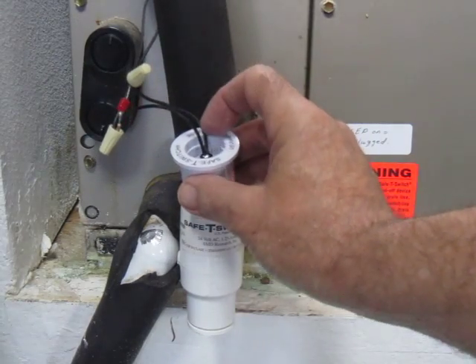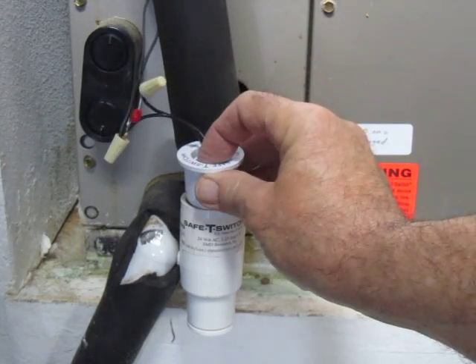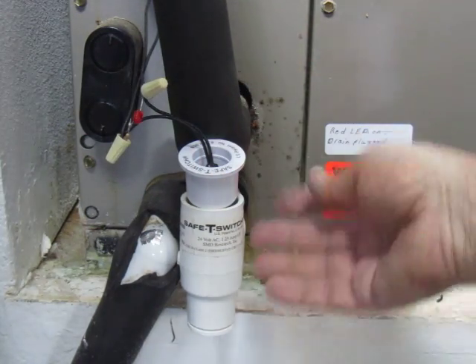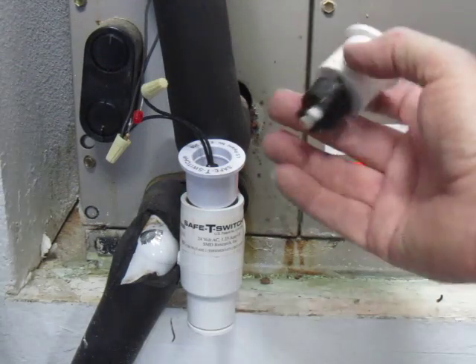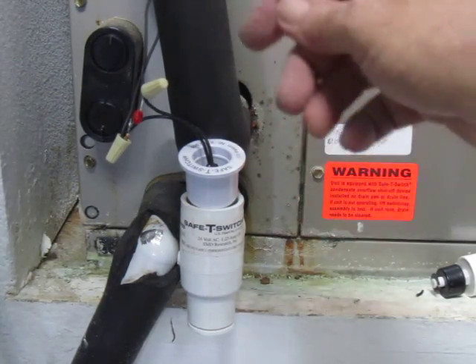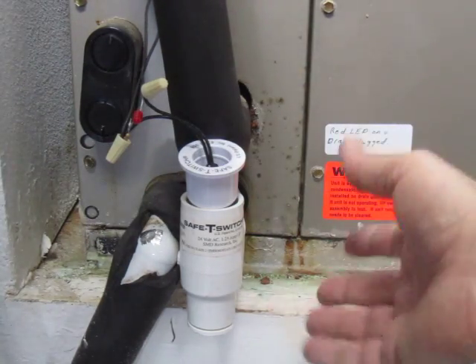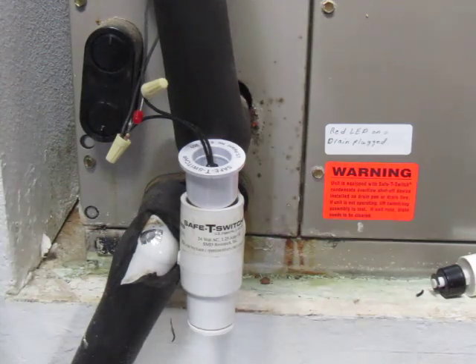Working with the safety switch that's designed to float up when your air conditioning system's drain plugs up, before you have water backing up. Mine failed — it stayed closed. It takes the 24 volts coming off the transformer and interrupts it so the control doesn't work for your air conditioner until you've resolved the problem, or is supposed to.